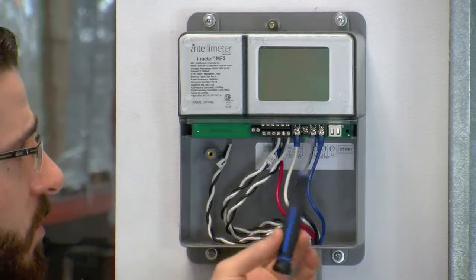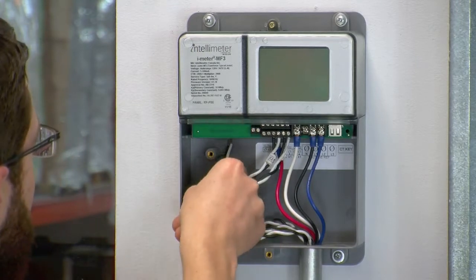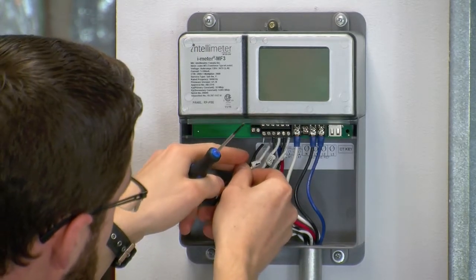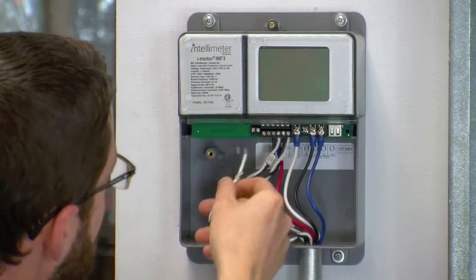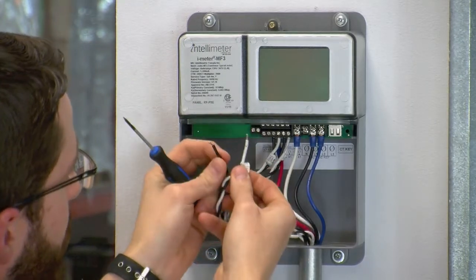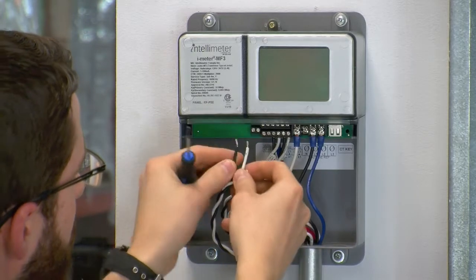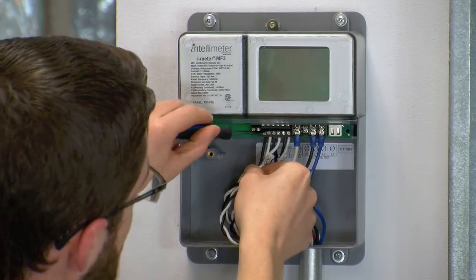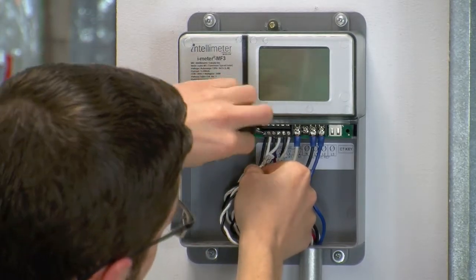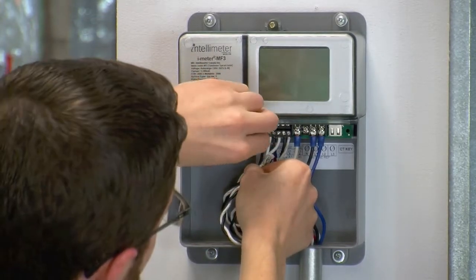So using a precision screwdriver, you're going to terminate the CT leads into their corresponding terminal strips. Here we use the bottom terminal strip for CTs 1, 2, and 3. So starting with CT1, we use black for negative and white for positive. As you go, you're going to want to double check your labels on your CT leads to ensure that each CT is being terminated into its correct slot.